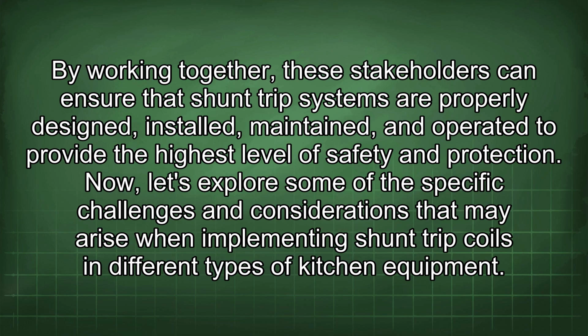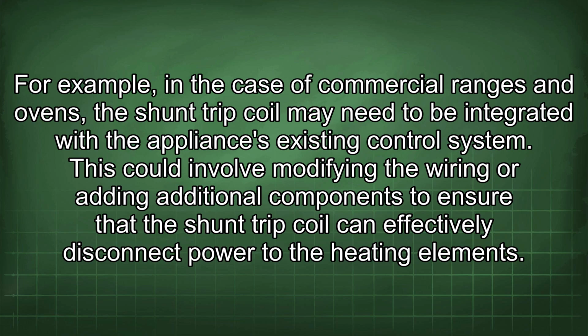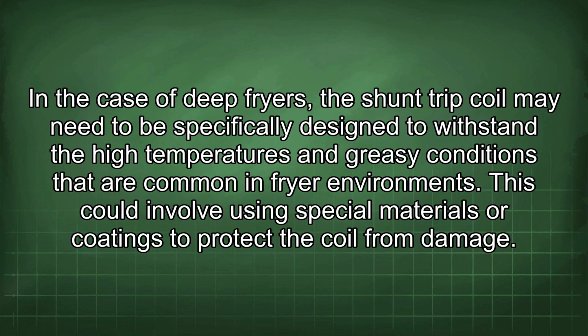Now, let's explore some of the specific challenges and considerations that may arise when implementing shunt trip coils in different types of kitchen equipment. For example, in the case of commercial ranges and ovens, the shunt trip coil may need to be integrated with the appliance's existing control system. This could involve modifying the wiring or adding additional components to ensure that the shunt trip coil can effectively disconnect power to the heating element. In the case of deep fryers, the shunt trip coil may need to be specifically designed to withstand the high temperatures and greasy conditions that are common in fryer environments.